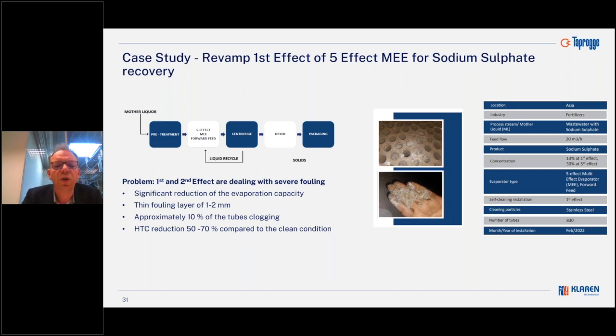So concentrating up to the moment of crystallization, and at the moment that the crystals were formed and had the appropriate concentration, in fact, they were taken out by a centrifuge. This plant experienced significant fouling in the first and second effect of the plant. Heat transfer, when we did the analysis, reduced by maybe almost 50 to 60%. And this was only by a thin layer, only 1 to 2 millimeters. So even a thin layer can already ruin your heat transfer to a great extent.